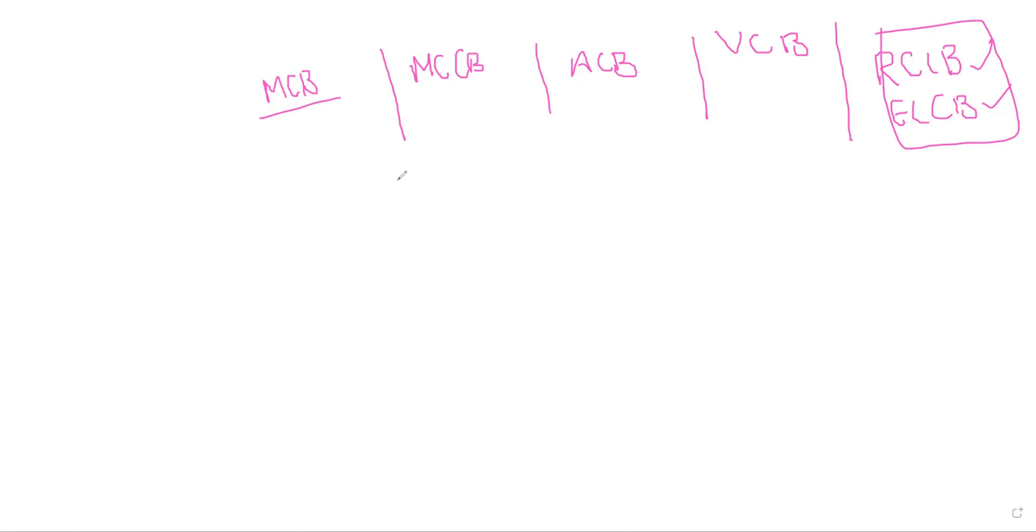So MCBs, in a simple way, if your rated current is not more than 100 amps, like 63 amps or 32 amps, or 16 amps, we can place the MCBs there. And here, the trip characteristics cannot be adjustable. They are standardized, standard trip characteristics.